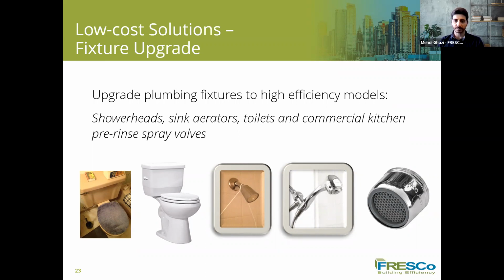Another area of interest when we are talking about maintenance is our fixtures, like our plumbing fixtures. So upgrading plumbing fixtures to higher efficiency models, like shower heads, sink aerators, toilets, and sometimes commercial kitchen spray valves. Most of our water consumption happens in these fixtures. So water efficient devices reduce water and sewer costs and reduce natural gas costs related to domestic hot water heating. Typical older shower heads consume between 2.5 to 5 GPM, gallons per minute, while water efficient shower heads and aerators reduce the consumption to 1 GPM.